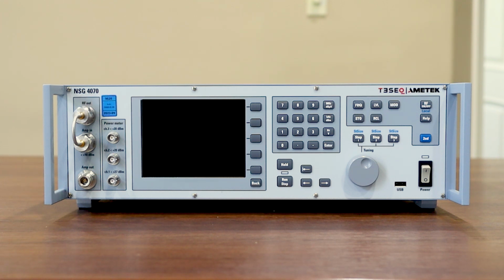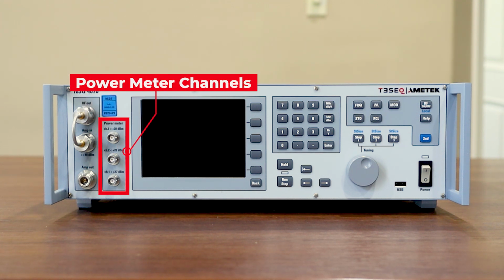As we work our way right, we have the 3 power meter channels. Power meter channel 1 is intended for adjusting the target value and for connection to the current monitoring probe. Channels 2 and 3 can be used to measure forward and reverse power with an external dual directional coupler. For additional information on integrating external amplifiers, go ahead and check out the other video we made on how to do that, and I'll put a link for that in the description below.